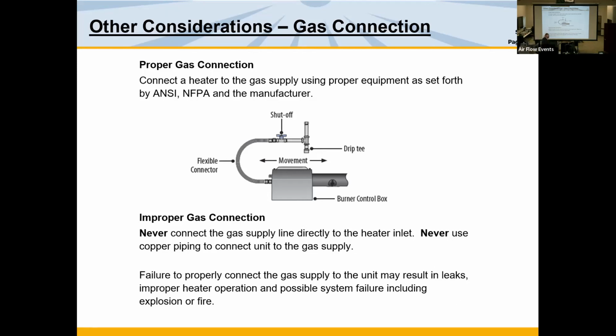We had a problem in Minnesota. The codes were improperly written. A lot of the contractors thought they needed to run copper directly to the heater. Expansion and contraction work hard. It's like taking a coat hanger and bending it 15 times. What happens? It breaks. Propane is under high pressure, very often in the building 2 pounds of pressure, and it quickly dumps and creates an explosive environment. We've had, unfortunately, some explosions, and thus the industry stepped in, and this gas connection still remains key.